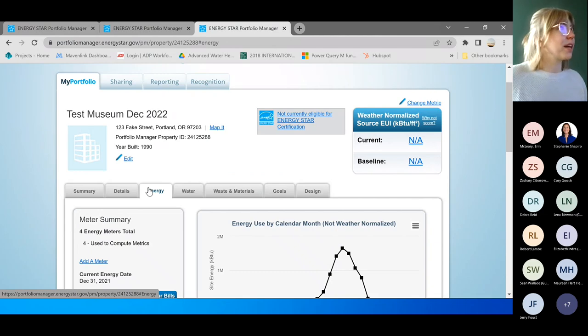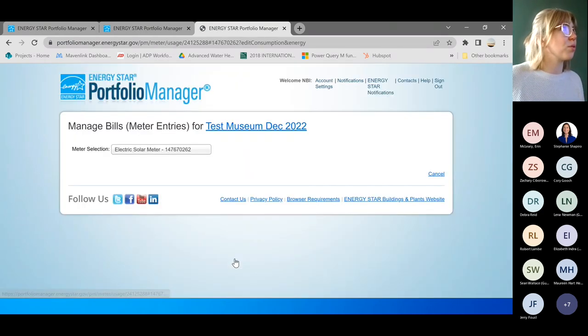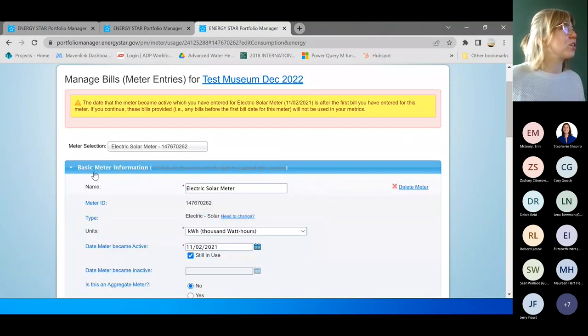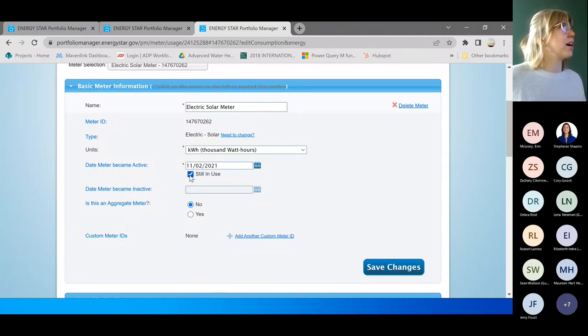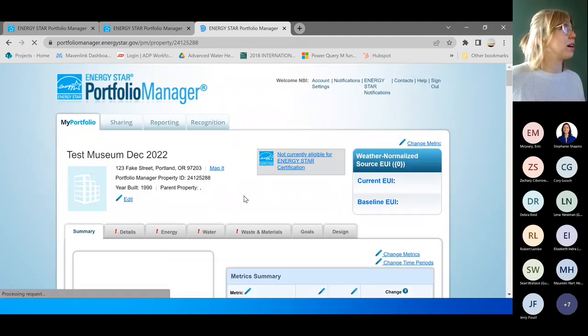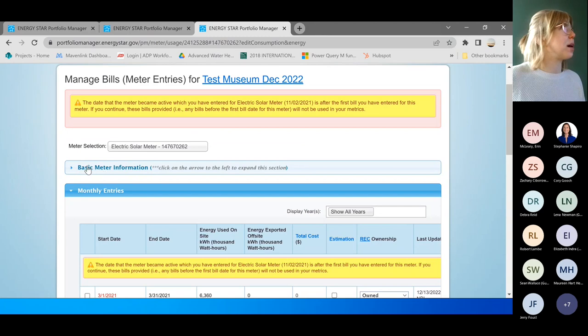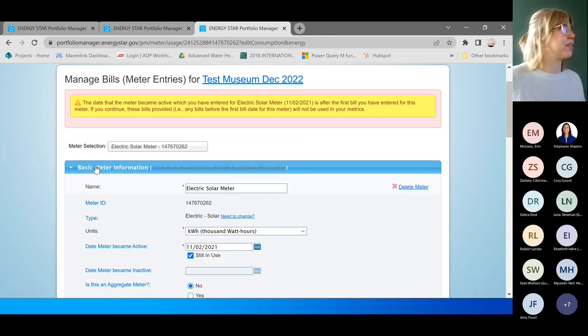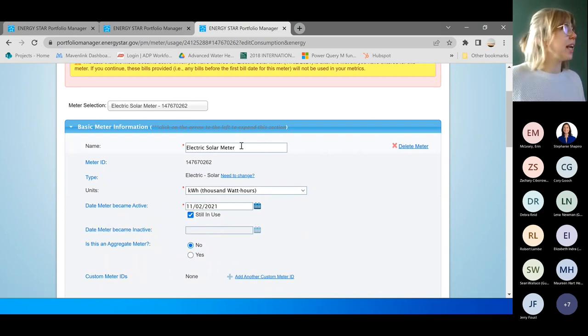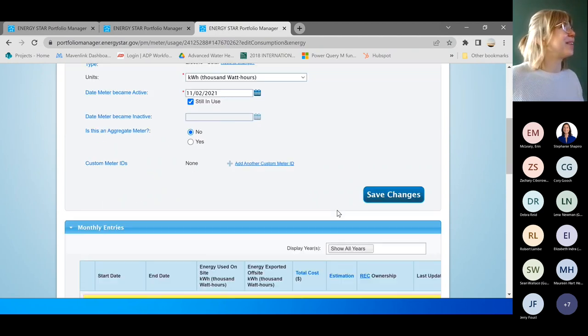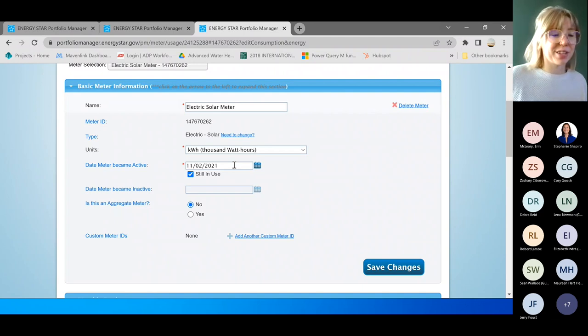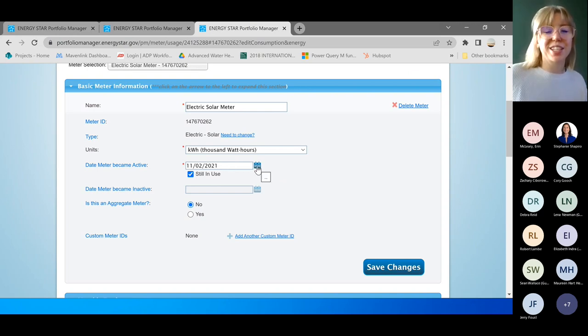If something changes about your meter — you want to change the name or it becomes inactive — you go to the Energy tab, scroll down to your meters table, click the meter, and there's a 'Basic Meter Information' section at the top that you click to expand. This is where you can update the name or correct the units — for example if you selected kWh when you meant kBtu. You can also update the date the meter became active if you entered it incorrectly.